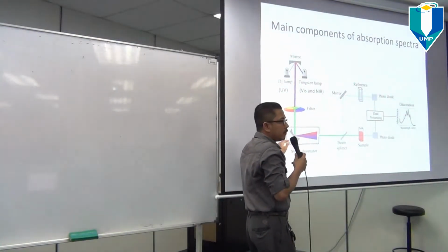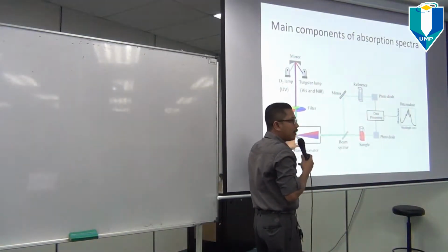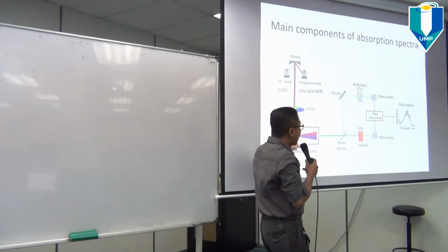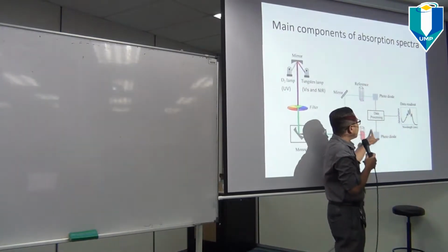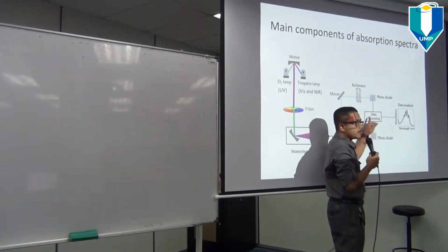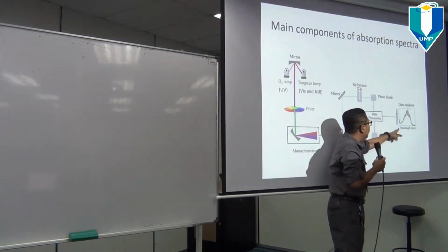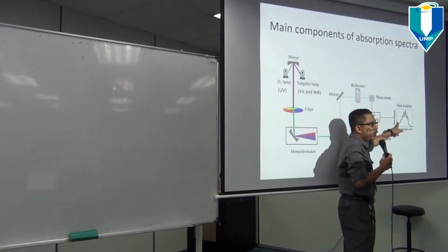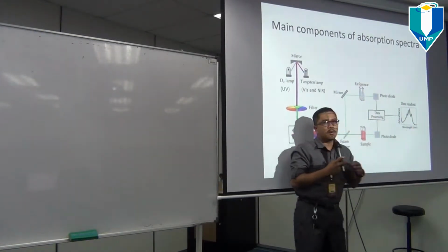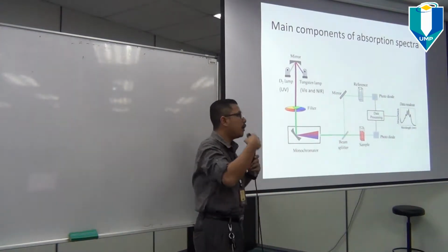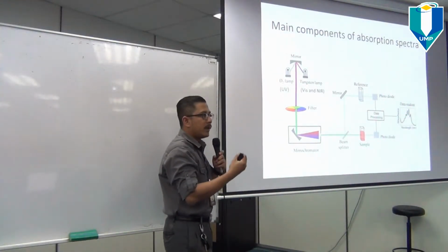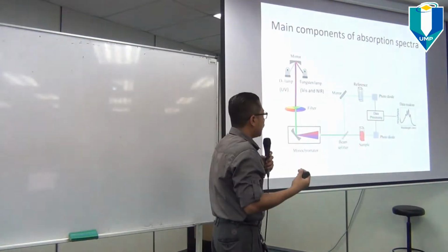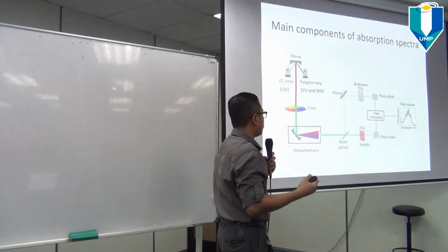After 200 nanometer, the monochromator selects 201 nanometer to pass through the monochromator to the beam splitter to the sample, and then the sensor of the machine will detect the intensity of absorbed light and plot the second point. 201 goes on and so on and so forth for 202 until 1400 nanometer. So the machine automatically detects and records the data for you.